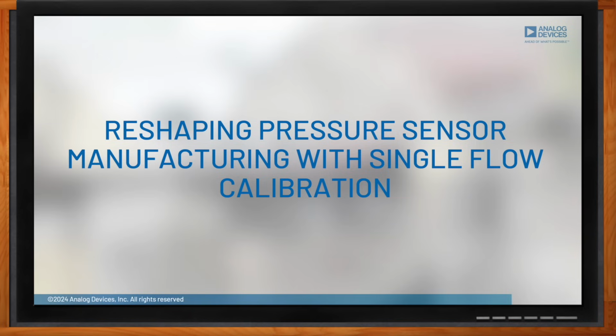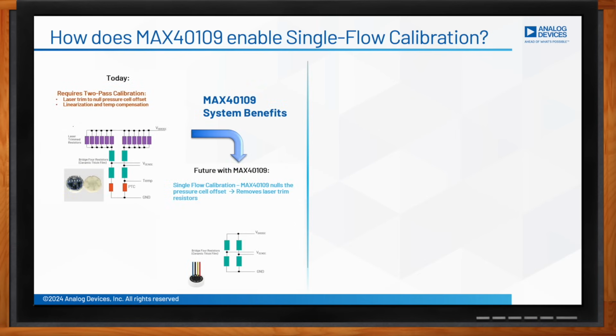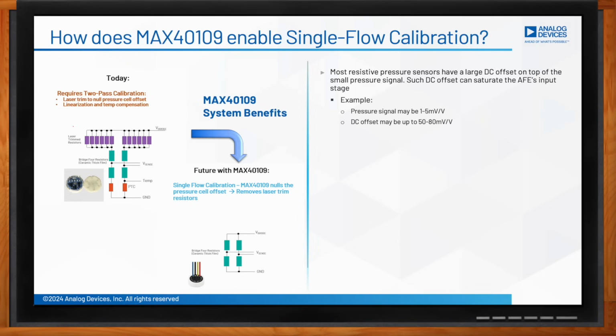Okay, so Maurizio, can you explain in more detail about that single flow calibration? So today's calibration goes through a two-step calibration process. Firstly, the pressure sensor resistive bridge is not ideal. Manufacturers must add laser trim resistors to null the pressure cell intrinsic offset voltage. The second step at PCB level performs a linearization and temperature compensation. This is because the pressure cell is intrinsically nonlinear and very temperature dependent.